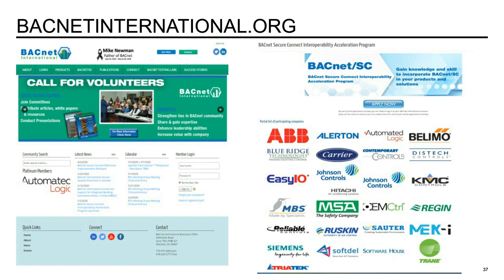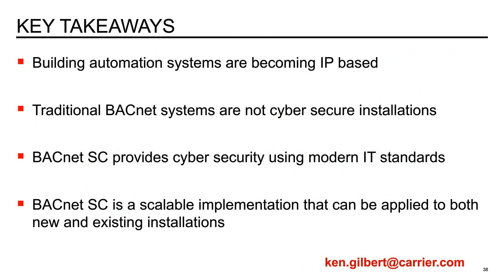So some key takeaways. Building automation systems are becoming IP-based. And as I mentioned, we're moving more from the IPv4 to the IPv6 protocol. Traditional BACnet systems are not cyber secure installations. BACnet SC provides the cybersecurity that's required by IT organizations using modern IT standards. And then BACnet SC is a scalable implementation that can be applied to both new and existing installations.